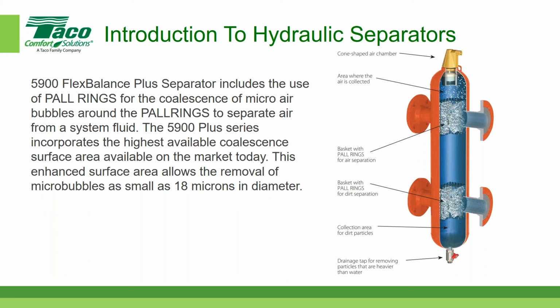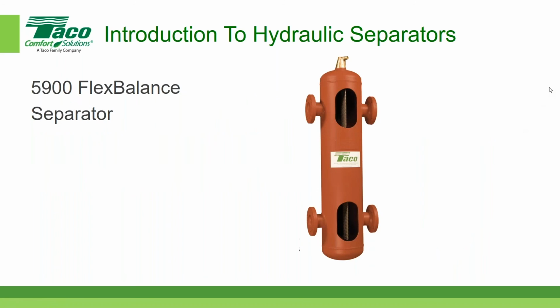If you came in at a 90, say a short radius elbow at the inlet, let's go back one more slide so it might be a little easier to see. If you came in over here with a short radius elbow, let's say at the inlet of the primary side, you'd have so much turbulence that you could create an unwanted pressure drop in the hydraulic separator, inducing flow in the secondary loop where you don't want it. So we generally recommend that you have a minimum of 5 pipe diameters at the flange connection, not the pipe connection size, but the flange connection.